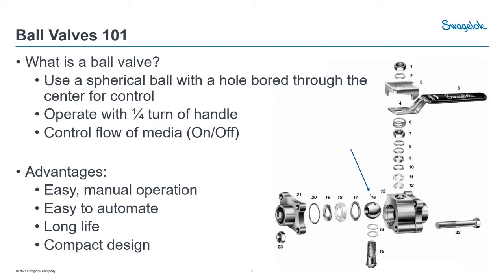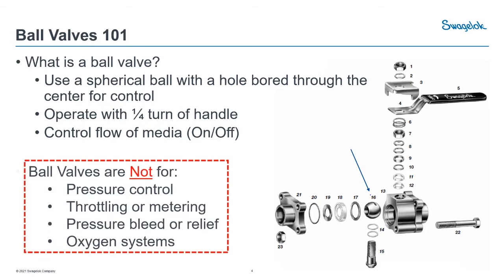One thing we want to cover is what ball valves are not for. They're for on-off and isolation. A ball valve is really not great for pressure control — once you start opening that ball a little bit, you pretty much have full pressure quickly because of its shape. It doesn't have any shape inside for metering, throttling, or pressure control. Also not great for pressure bleeder relief: it's going to dump your system really fast, which might be bad for your system.